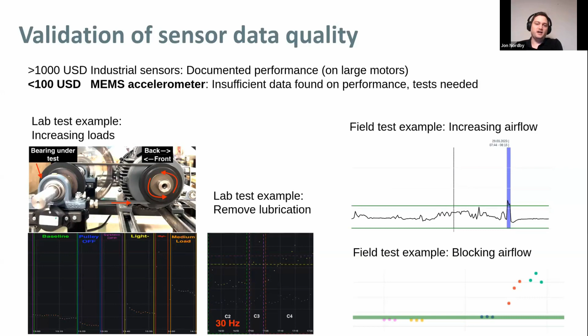We realized quickly that what is considered normal for a machine varies a lot depending on the particular machine. There are variations based on physical properties such as equipment type, brand, and model, even within the problem space of air handling units, as well as sensor placement and attachment method, which needs to be adapted to each device since they're not designed for mounting sensors.